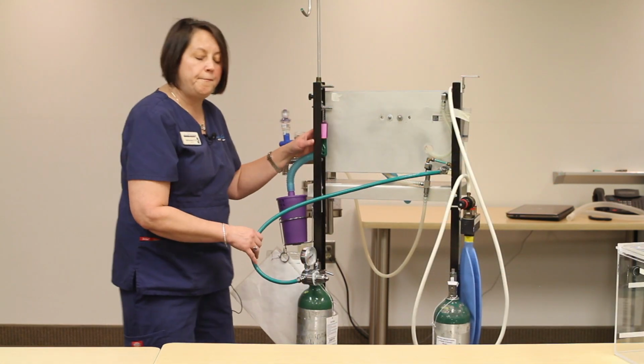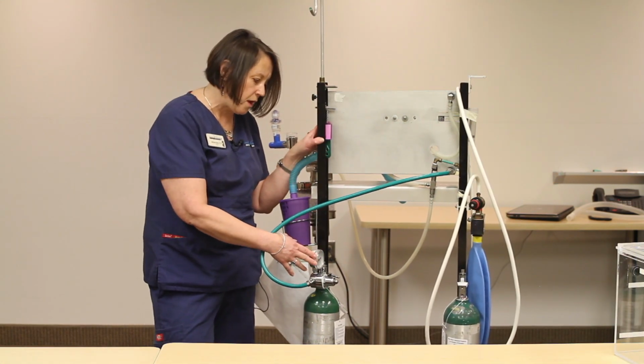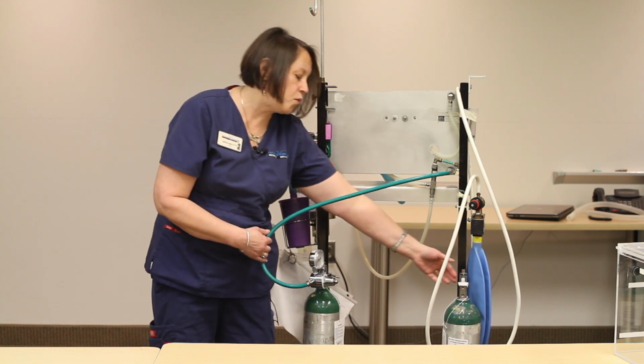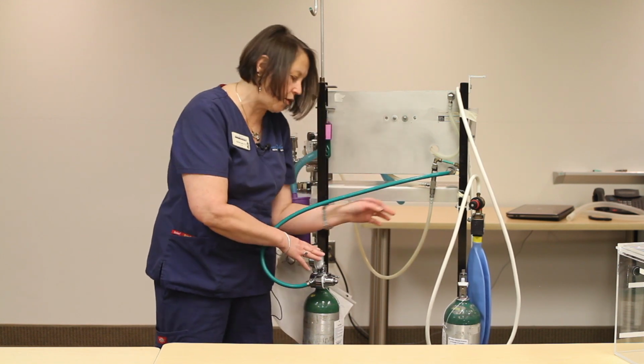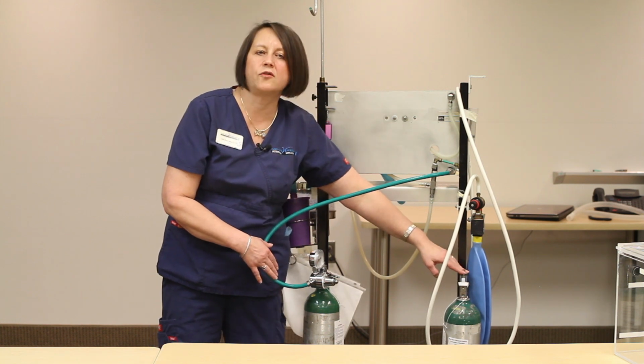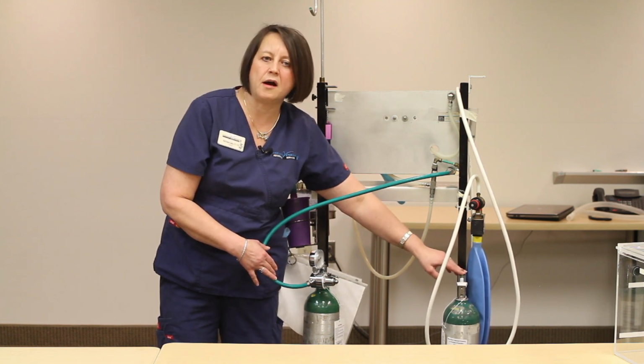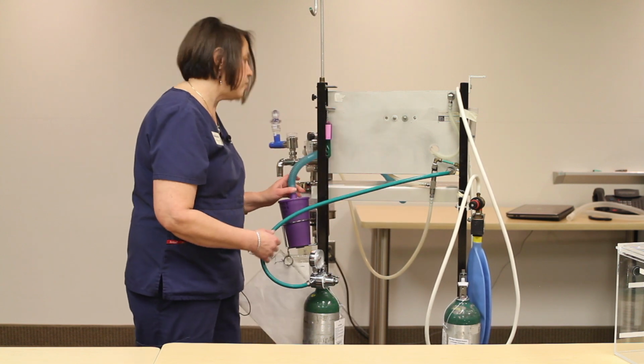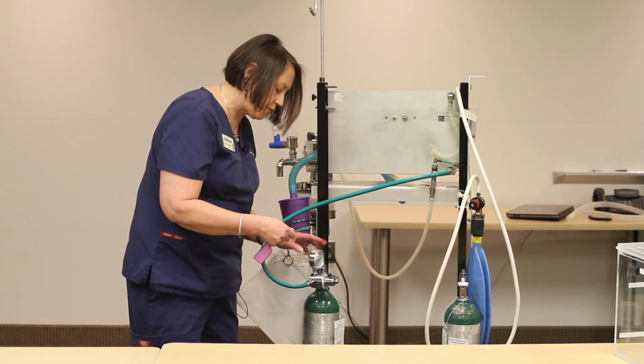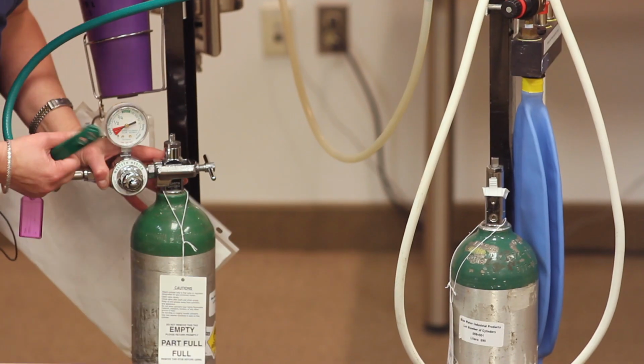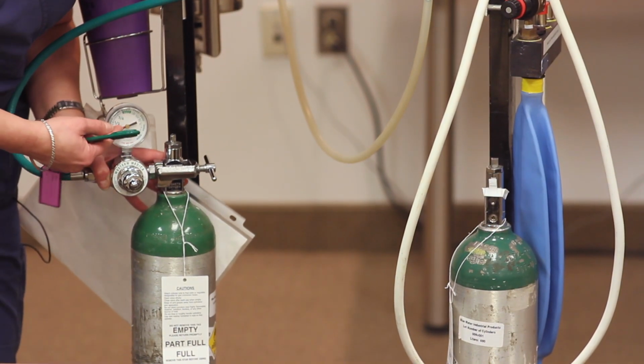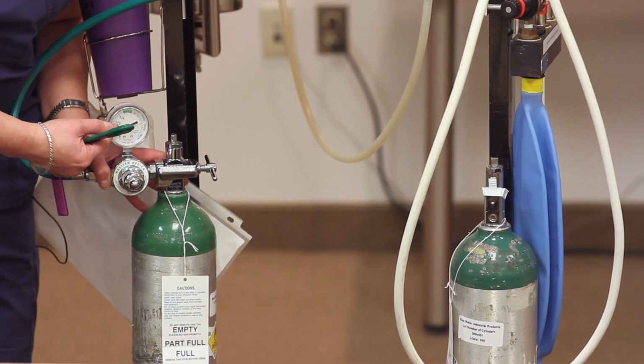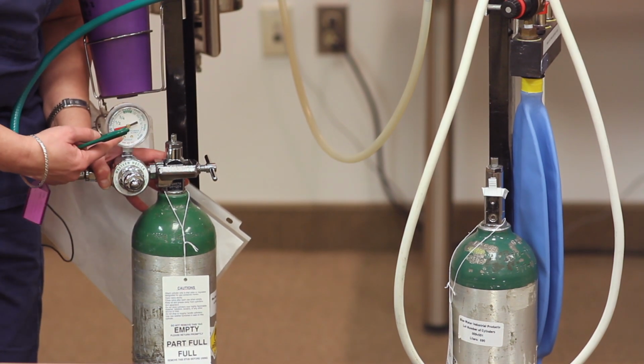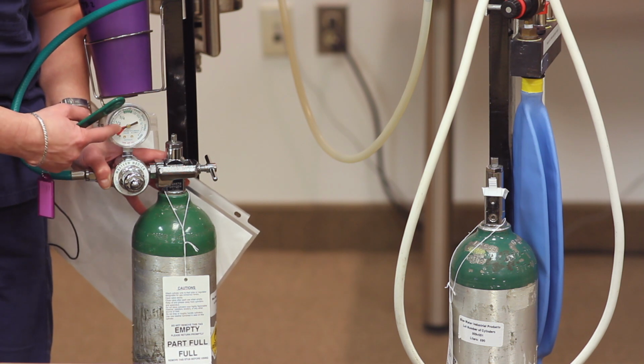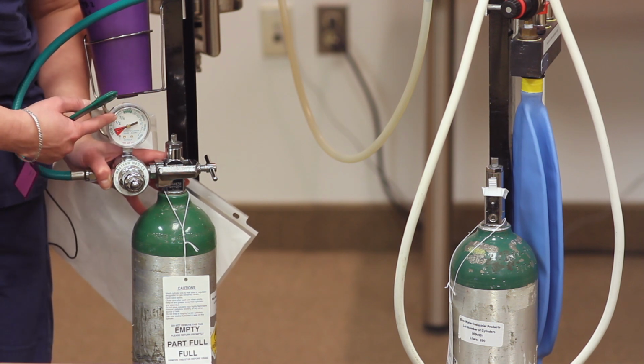To change the pony tanks on this machine, you always want to make sure that there's a new one in place. So if this one runs out, you do have a new one. These new ones are kept in the basement in the oxygen room. But what you will do to change the pony tank is, the first thing you're going to need to do is make sure that it actually is empty. This needle is in the red, but the needle actually can go all the way down to that post, and there is quite a bit of use still to this machine. But I'm going to go ahead and show you how to do it for demonstration purposes.